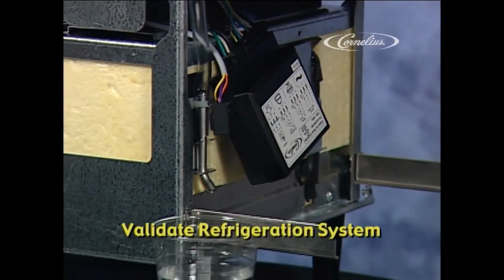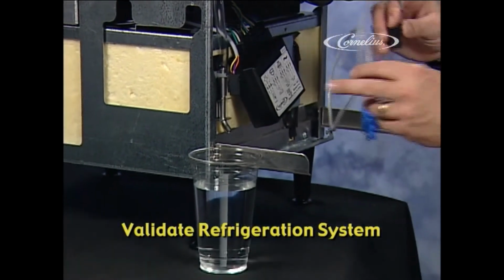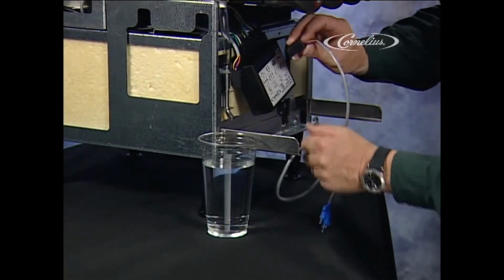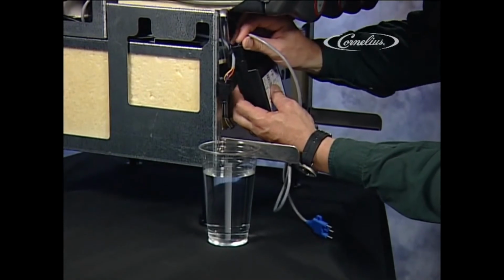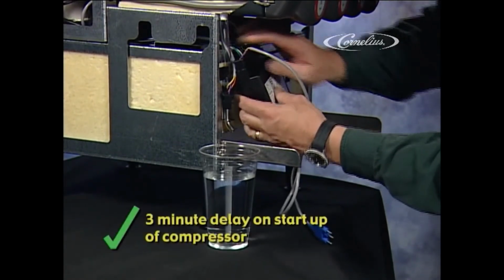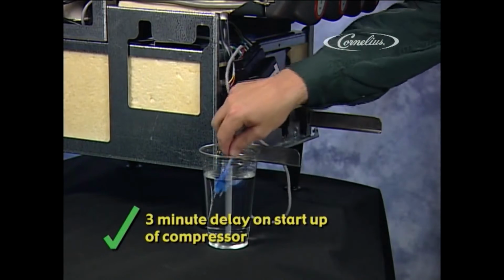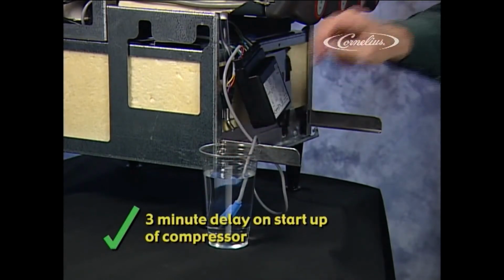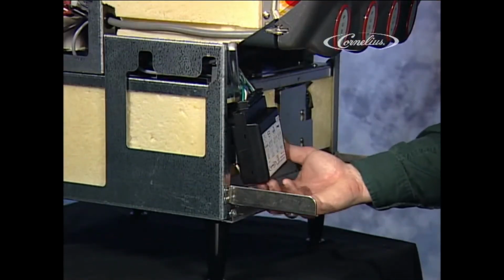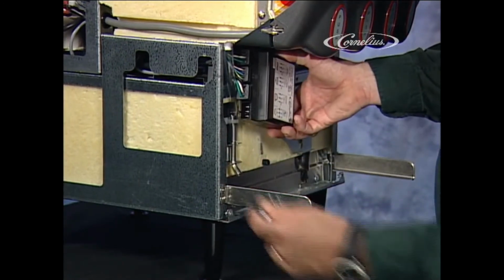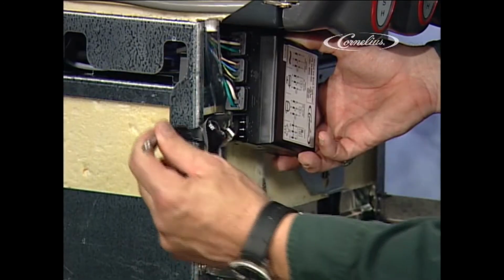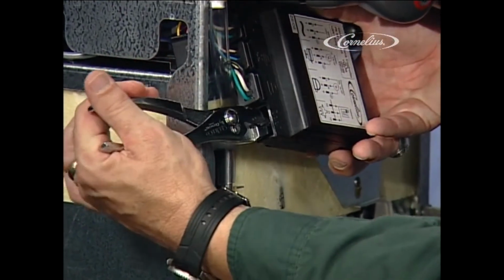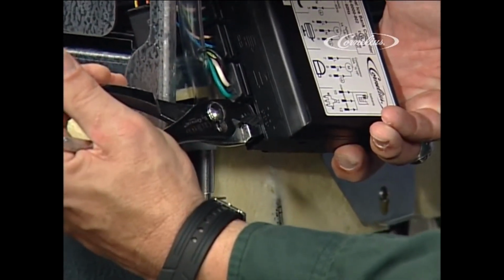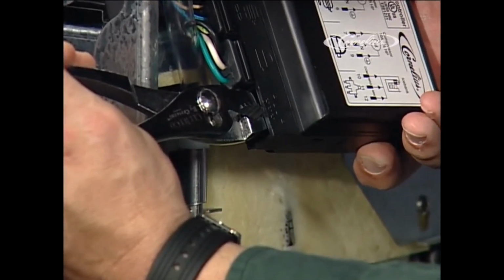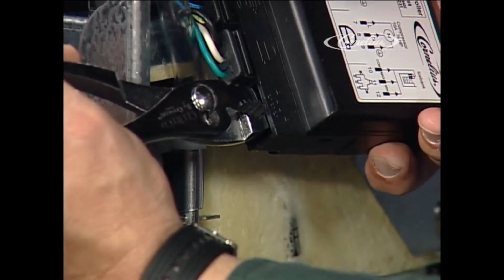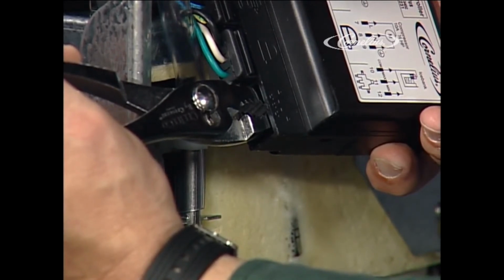Now we are ready to validate our refrigeration system. There are two ways to accomplish this. One, if we have an extra loose probe, we can plug that in the slot and place it in a glass of tap water. After the 3 minutes, the ice bank control or IBC should activate the fan and compressor. If we don't have an extra probe, we can accomplish the same result by taking a pair of pliers, gripping the middle connector or terminal, and at the same time touching the other two. We are simulating the probe being covered with water, thus closing the circuit. Again, after waiting the 3 minutes, the condenser fan and the compressor should start.